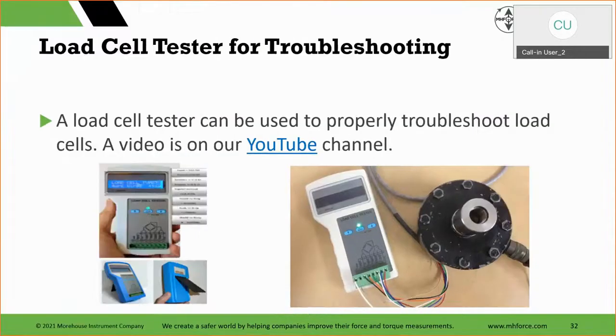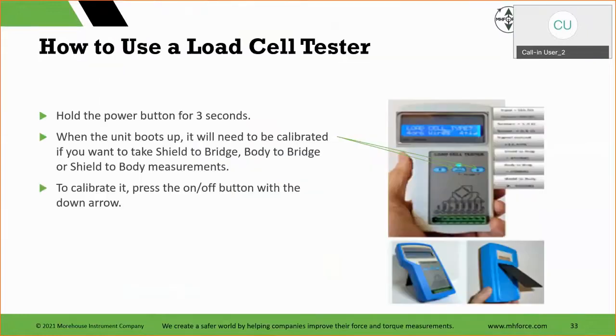And if you have this slide deck, you can see the load cell videos on our YouTube channel of the tester. It's really easy. You hold the power button for 3 seconds. When it boots up, it will need to be calibrated if you want to take shield to bridge, body to bridge, or shield to body measurements. These are things, the instructions are there. Press on and off with the down arrow. And what that's really doing is it's sensing. It's going through the whole load cell, checking the circuits, checking everything else, and then you can scroll through and you can see all these readings.